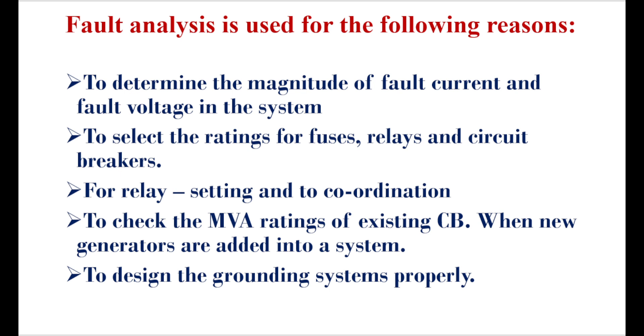Fault analysis is used for the following reasons: to determine the magnitude of fault current and fault voltages in the system; to select the rating of fuses, relays, and circuit breakers for relay setting and coordination; to check the MVA rating of existing equipment when new generators are added to the system; and to design the grounding system properly.